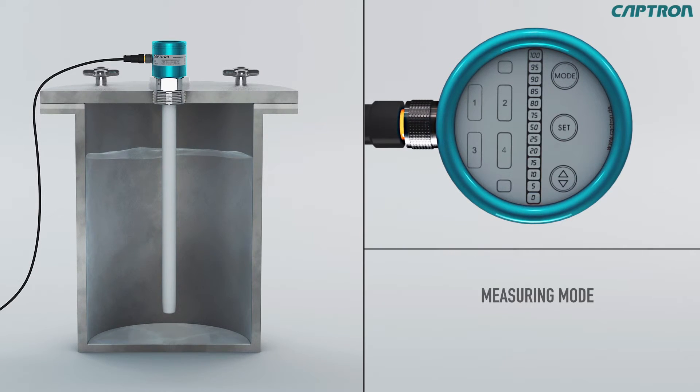Now the probe is operational and displays the current fill level. During the adjustment of the minimal value, the following error messages may occur: MN lights up red, 85 to 95 percent, and the minimal value last set blinks green. In this case, the set minimal fill level is the same or larger than the set maximal fill level.